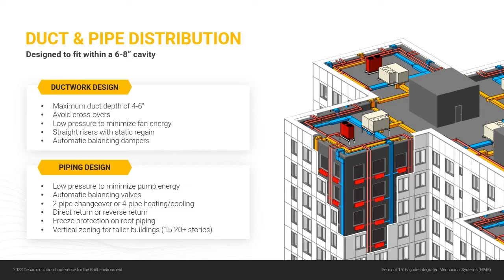Now, the duct and pipe distribution is being designed to fit within a narrow cavity between the existing facade and the new facade. And that cavity will mostly be in the 6 to 8 inch range. So the duct and pipe has to fit within that space. In terms of the duct design, we need to keep the ductwork to a maximum depth of 4 to 6 inches. And another thing that's very important is to lay it out without any crossovers, because with only 6 inches, there's no way we're going to have any crossovers of the ductwork.